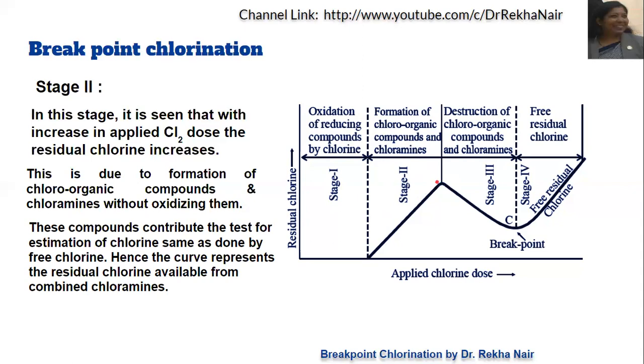However, it is not true residual chlorine that is increasing. The actual increase is in the amount of chloro-organic compounds and chloramines being formed, and because these compounds test similarly to chlorine, we assume residual chlorine is increasing. But in reality, Stage 2 is characterized by the formation of chloro-organic compounds and chloramines — not free chlorine.